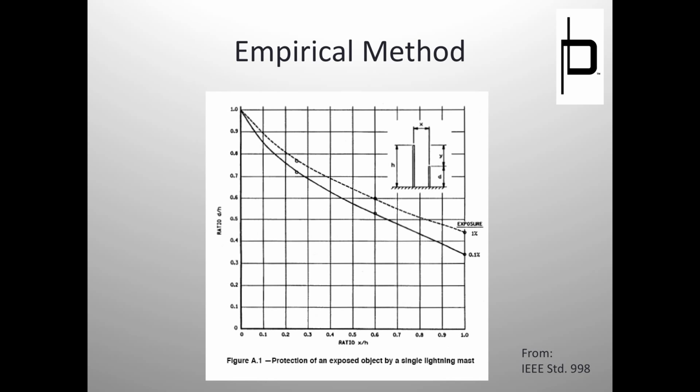Excuse me, 6.5 feet. I apologize. No, wait, I'm sorry. 65 feet. Yeah, certainly. Sorry, I was thinking 10-foot equipment height, but no. We're talking a 100-foot mast. So my X to H would say, okay, 65 feet away, you can place equipment that is 50 feet tall from a mast that's 100 feet tall, right? Correct, 100 feet tall. What did I say? You said 100 feet away. My bad. 65 feet away. Okay, sorry, juggling a lot of numbers in my head here.